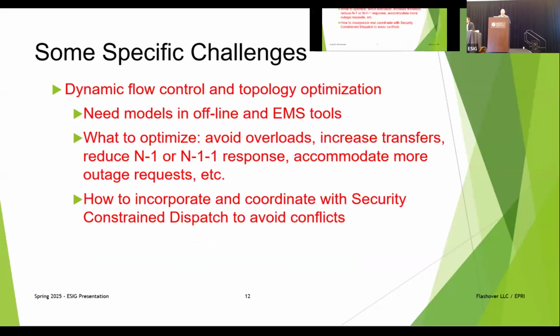Dynamic flow control and these topology optimizers. A lot of folks have seen presentations on that. Well, offline tools, PSSE, PSLF, they don't have models in them. And the EMS system sure as hell doesn't have models in it. And you're going to have to write a healthy $1 million check to GE and Siemens to start putting these things in your EMS system.